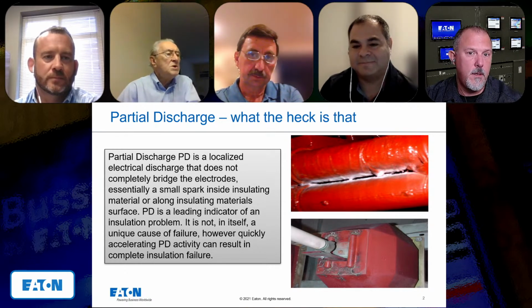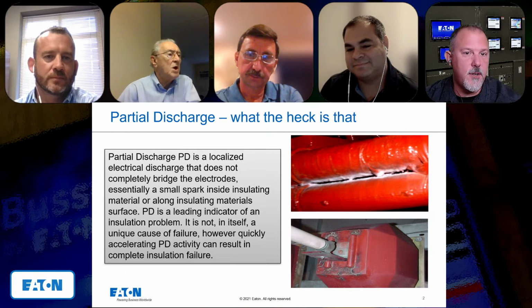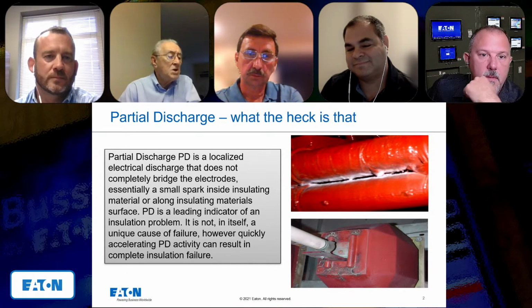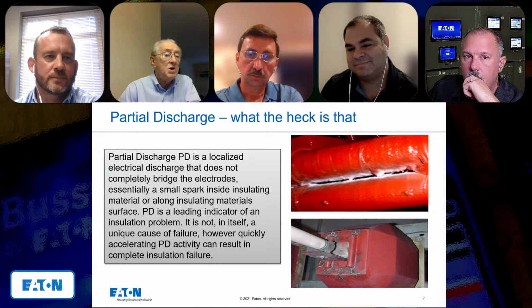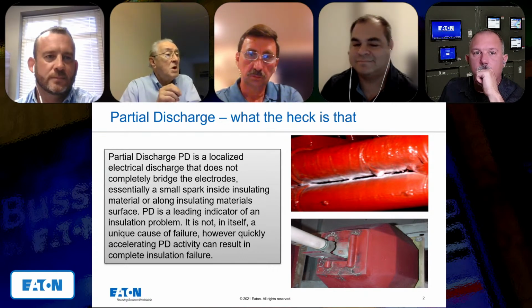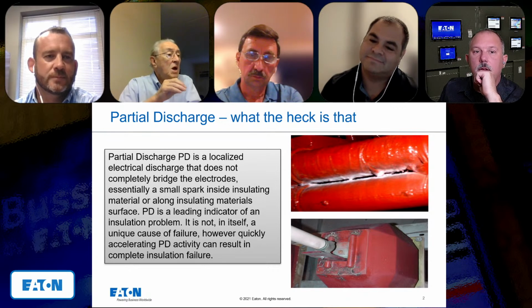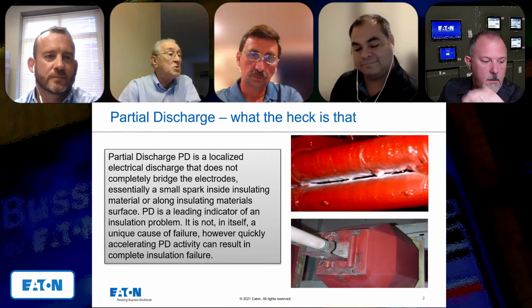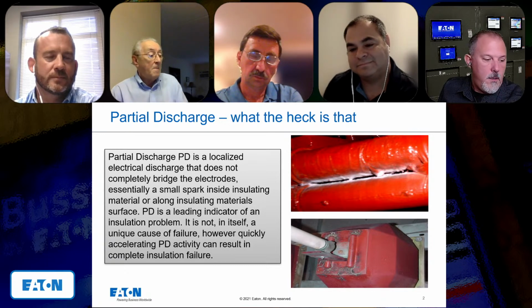Well, it is not leakage current. It's not leakage current? Okay. It is, again, a little spark which occurs in the void inside the insulation and on the surface of the insulation when there is heterogeneity of the structure, when there are different types of insulation, some contamination possibly, or inclusions.